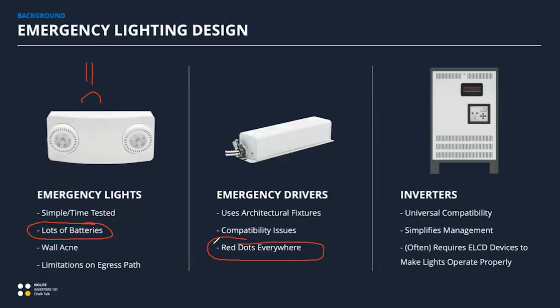There are also some compatibility issues to be aware of with emergency drivers. They're a little difficult to specify electrically—you actually pick the highest wattage LED driver that's still under the wattage of the fixture. So if you have a 35 watt fixture, you might have a 25 watt LED driver. In practice, that means you're not going to get full illumination out of the fixture in emergency mode.